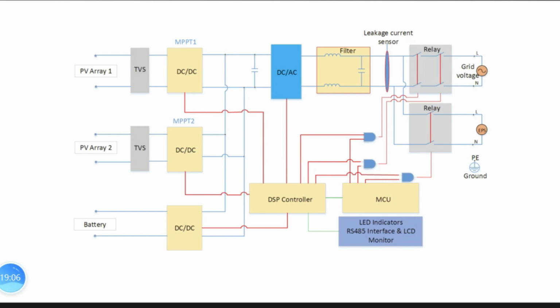And the unique of we use the latest generation of the TI digital processor that will help the inverter become more intelligent and smart. So we have more efficiency from the MPPT maximum power point charging, and from charging points they have more efficient compared with other competitors. And also the inverter will have a quicker response to this switch time during switch on-grid mode to off-grid mode. Normally all of the inverters can finish the switch time within 10 milliseconds. And other intelligent protection like over and low voltage or over and low frequency protection and temperature protection as well.